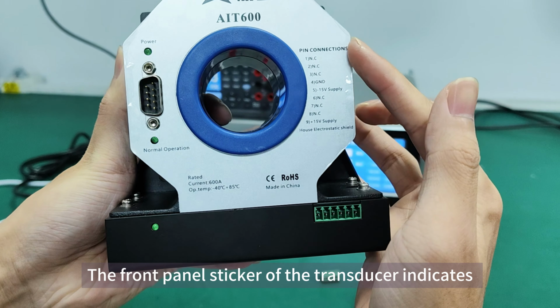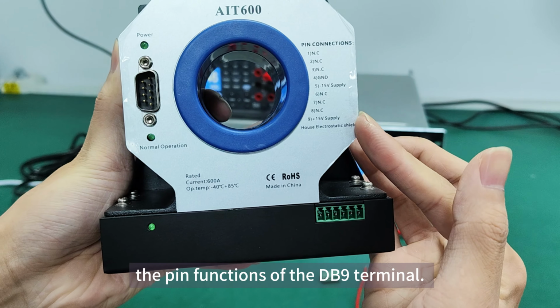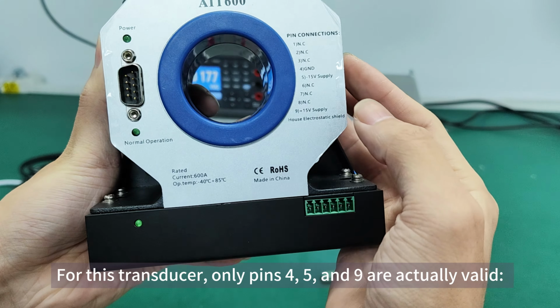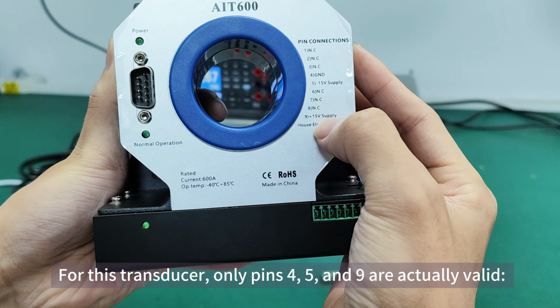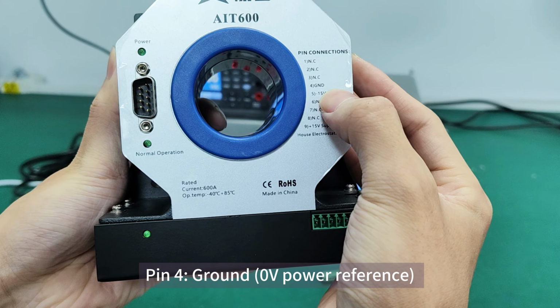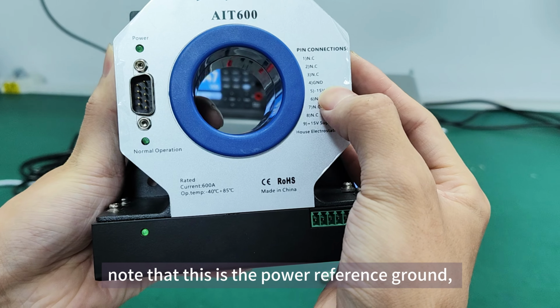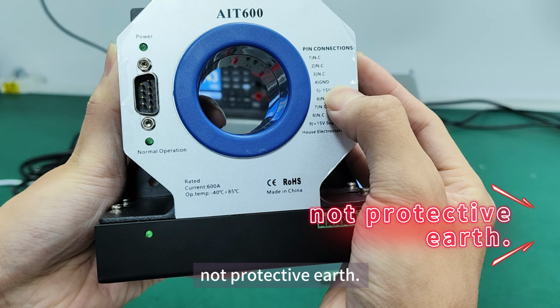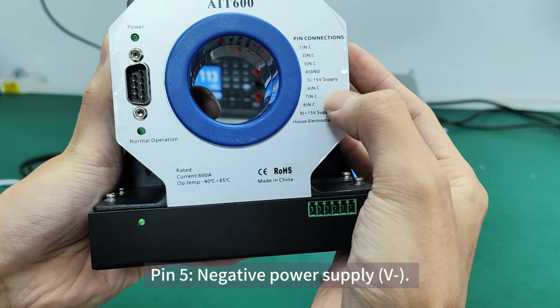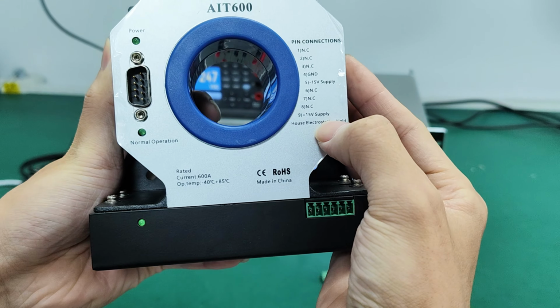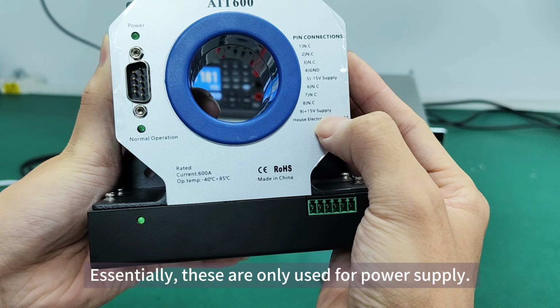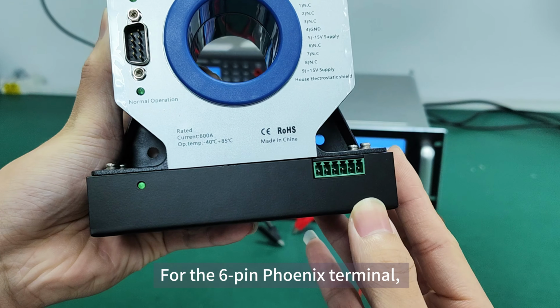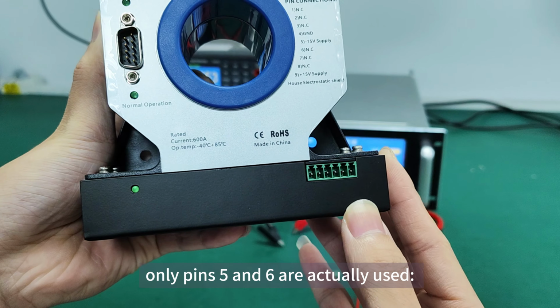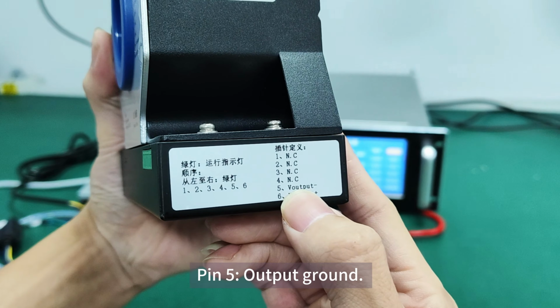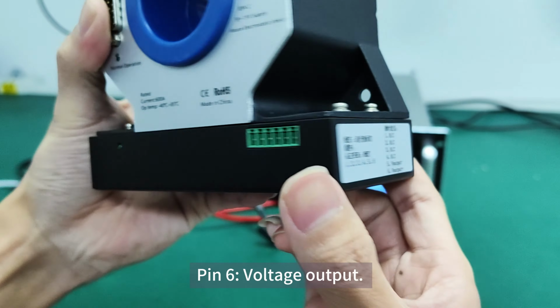The front panel sticker of the transducer indicates the pin functions of the DB9 terminal. For this transducer, only pins 4, 5, and 9 are actually valid. Pin 4, ground. Note that this is the power reference ground, not protective earth. Pin 5, negative power supply. Pin 9, positive power supply. Essentially, these are only used for power supply. For the 6-pin Phoenix terminal, only pins 5 and 6 are actually used. Pin 5, output ground. Pin 6, voltage output.